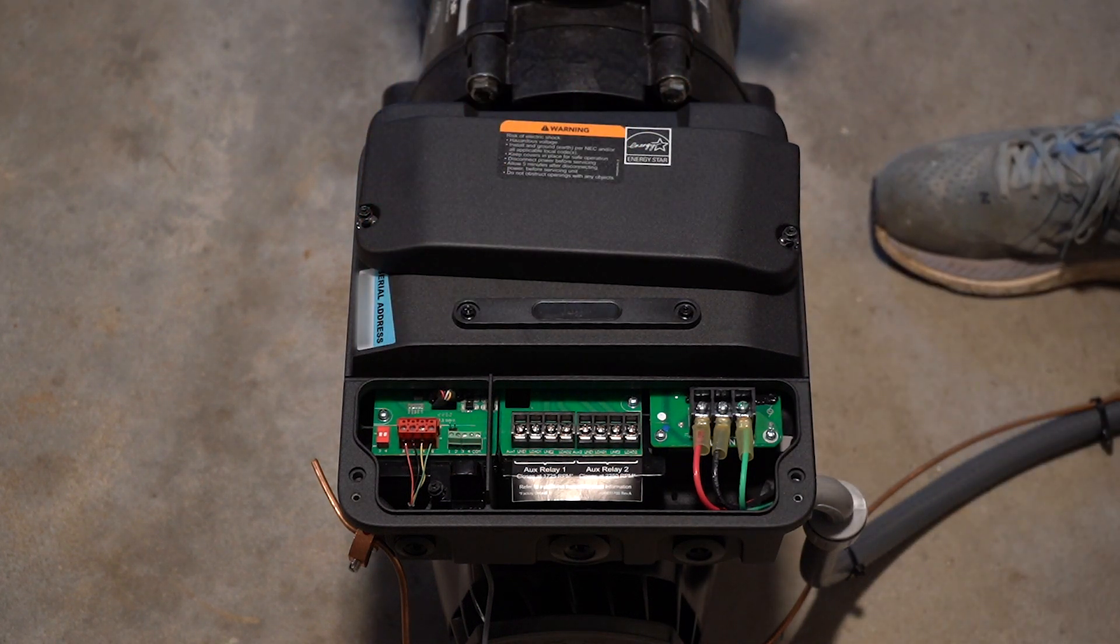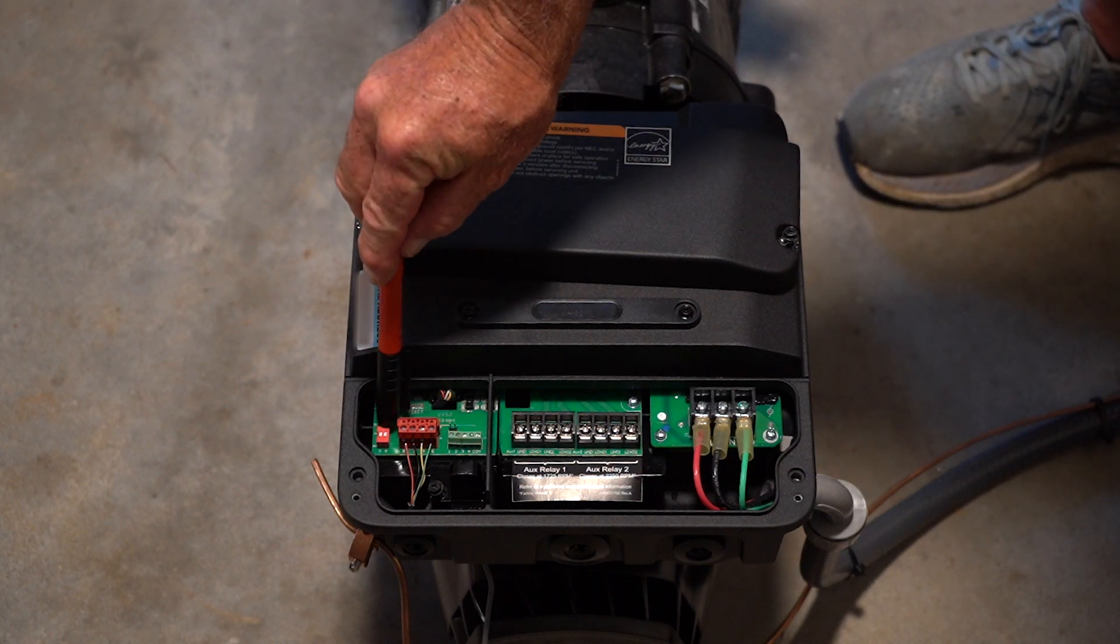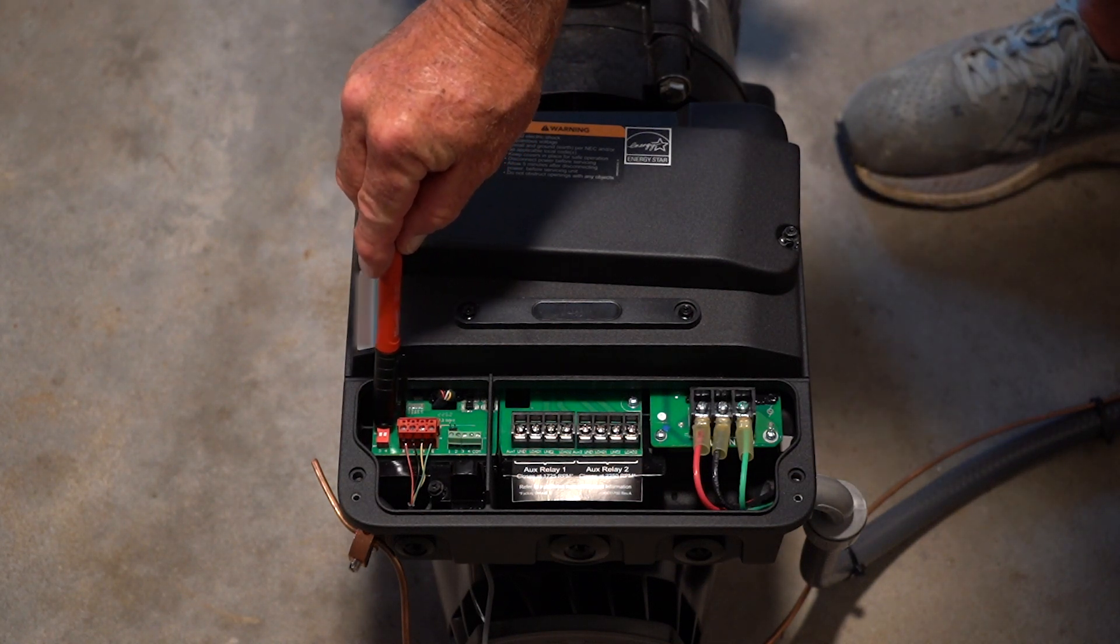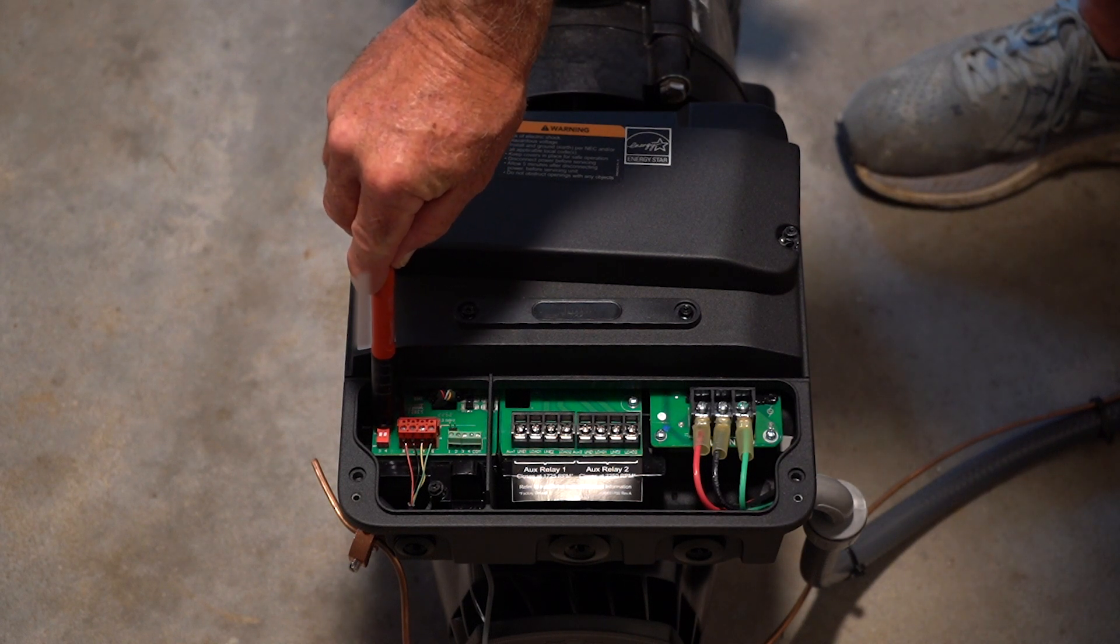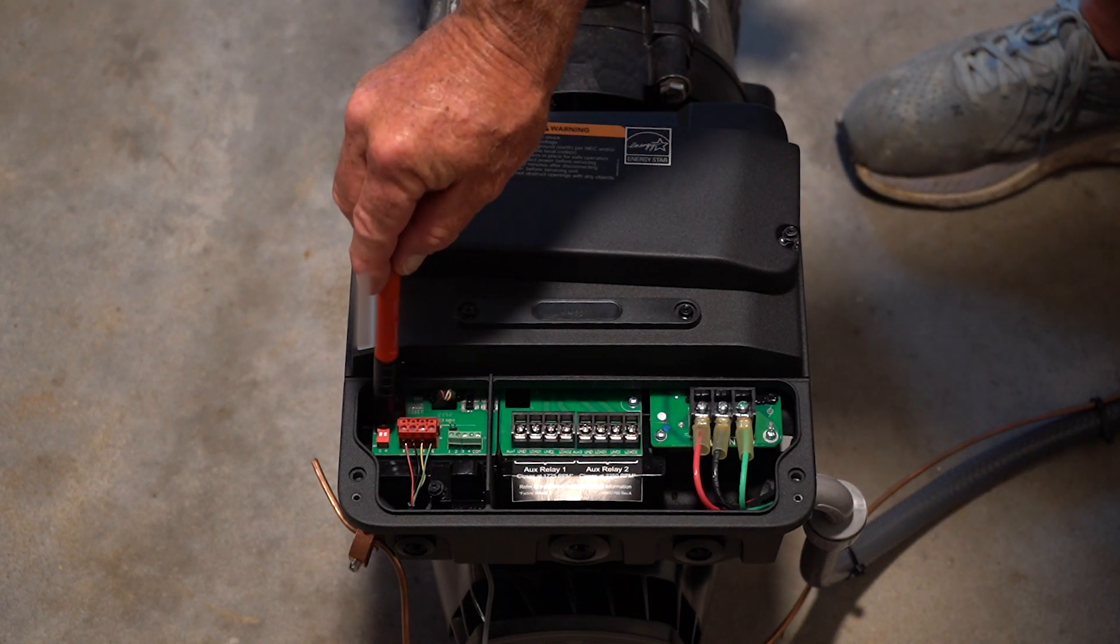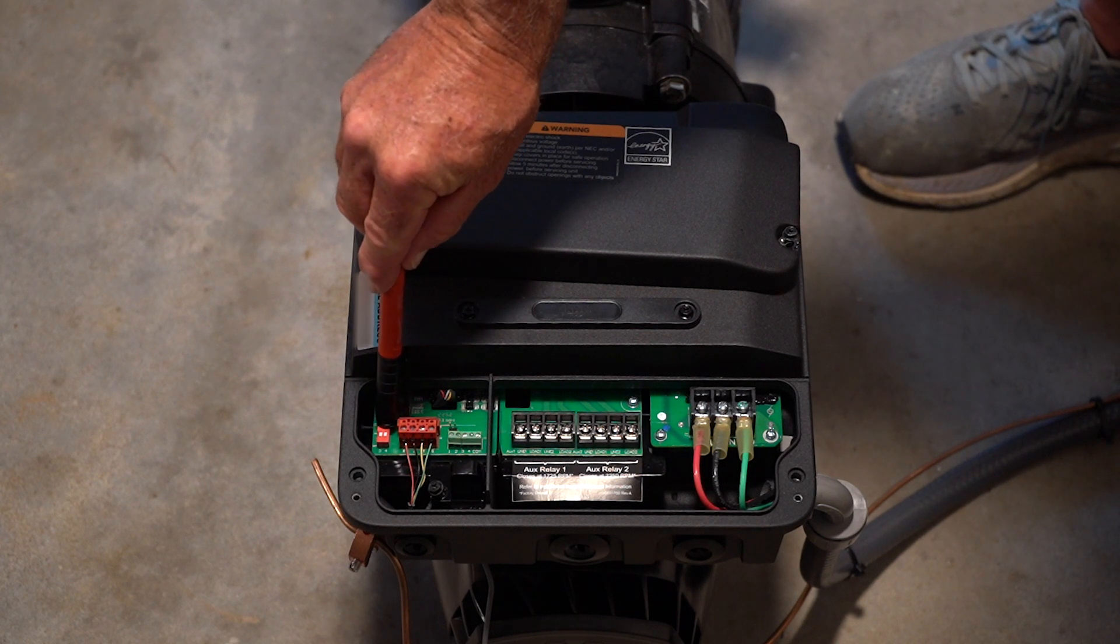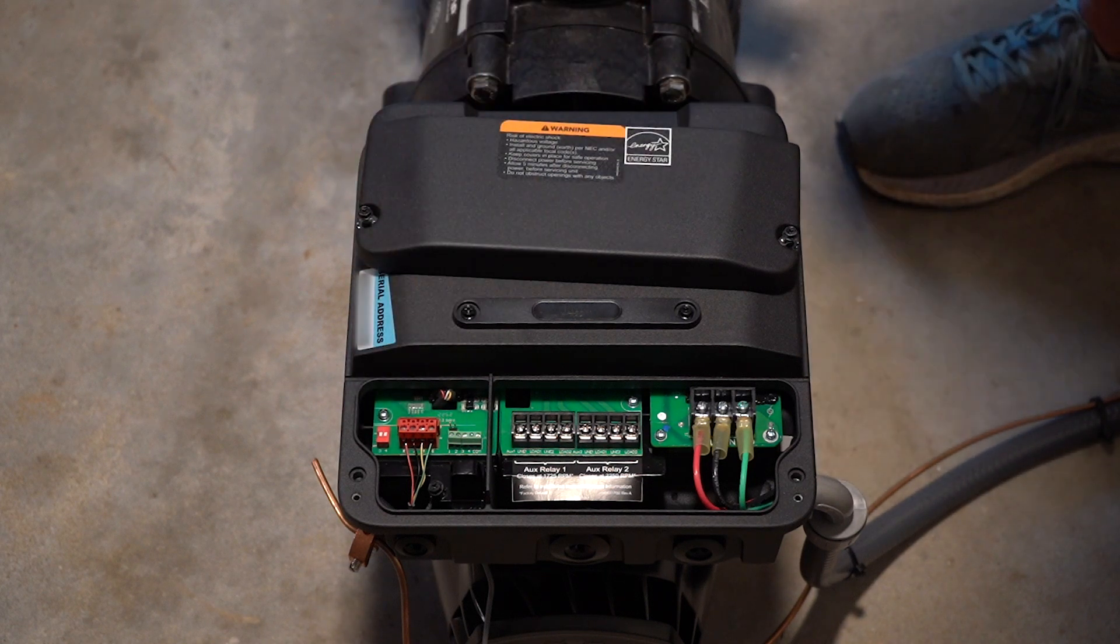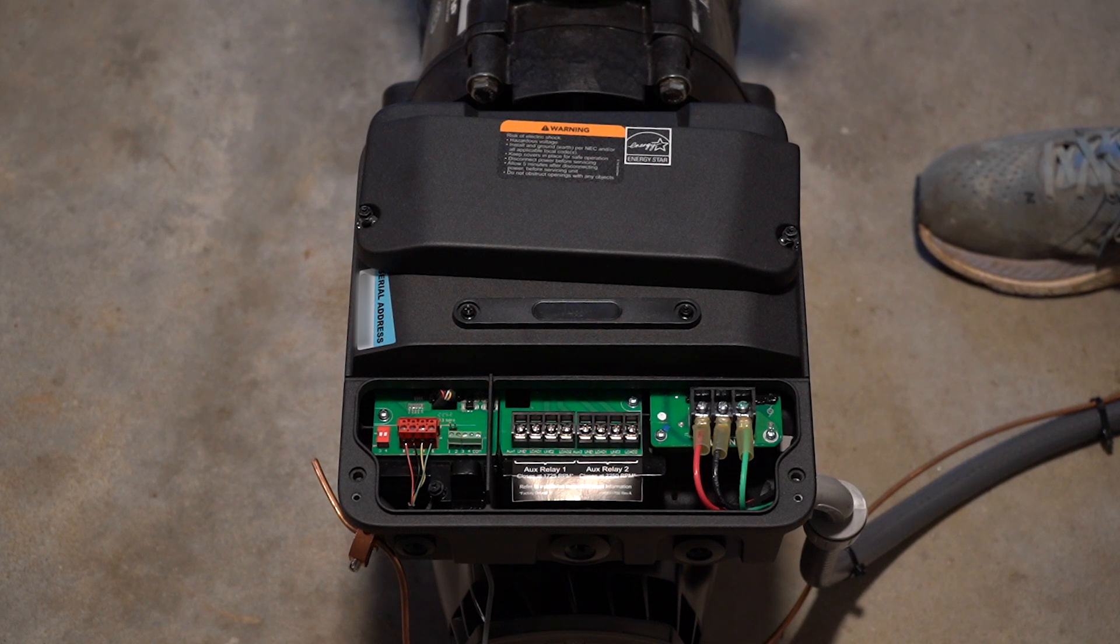So if you had what I'll call the legacy or an older system, you can use these dip switches to assign the variable speed pump. So with switch number three and four in the down position, this would be technically address one. And then if you flip up switch number three, it would be address number two. If three was down and four was up, address number three. And then if they're both up, address number four. That is all that they allow you on the legacy system.